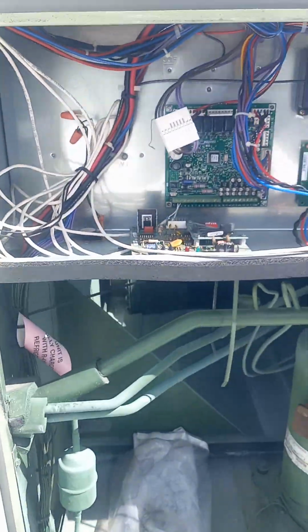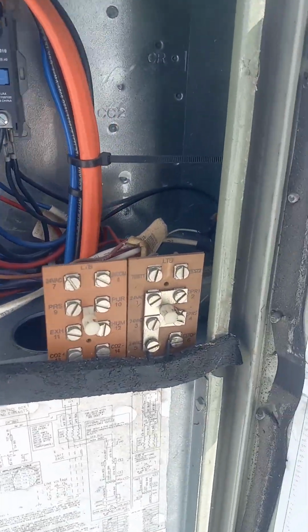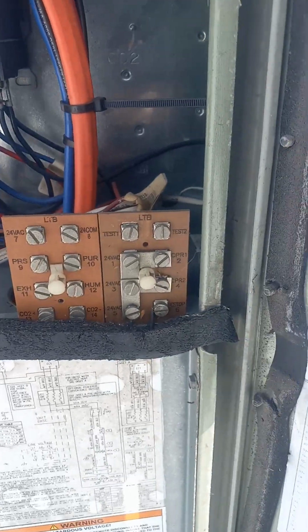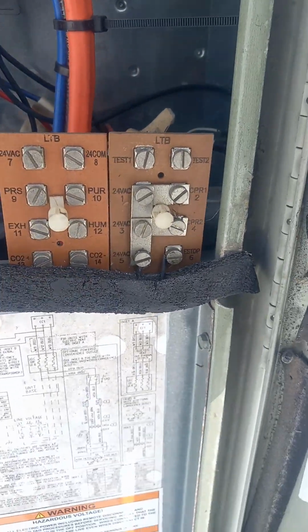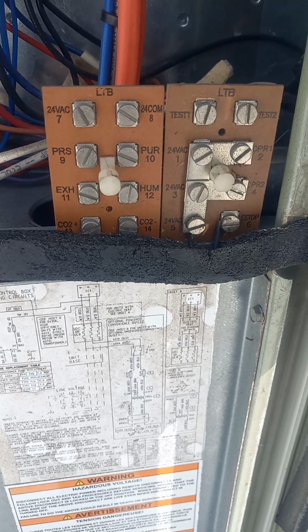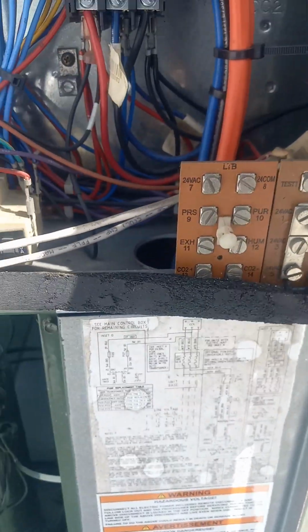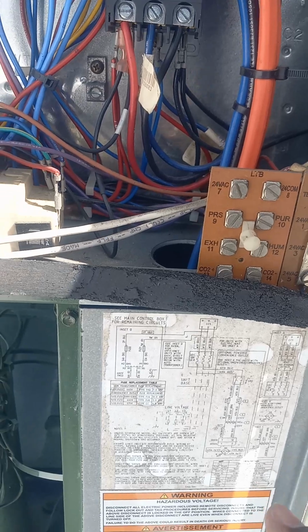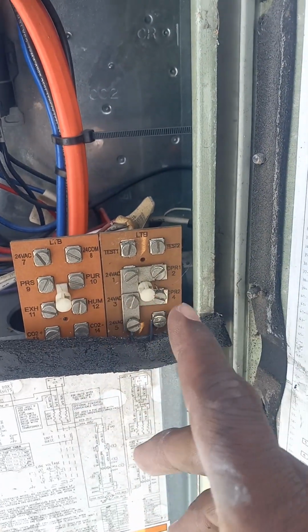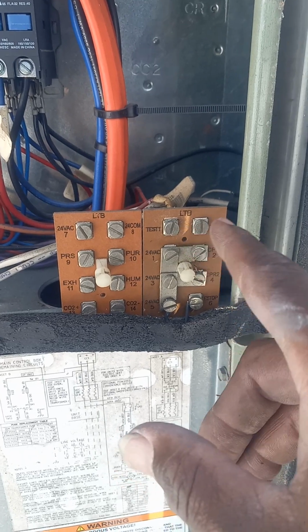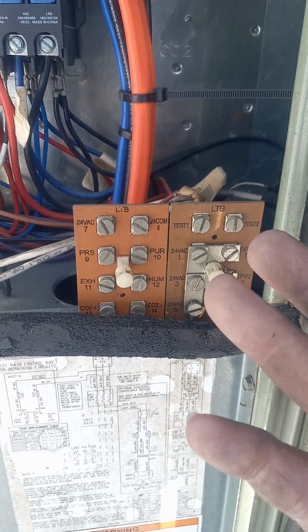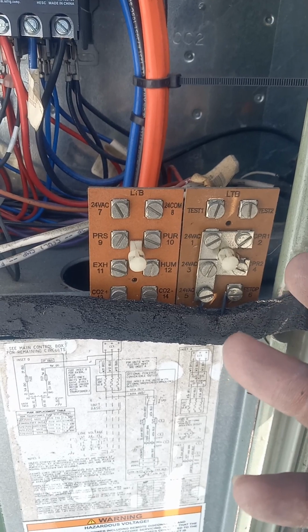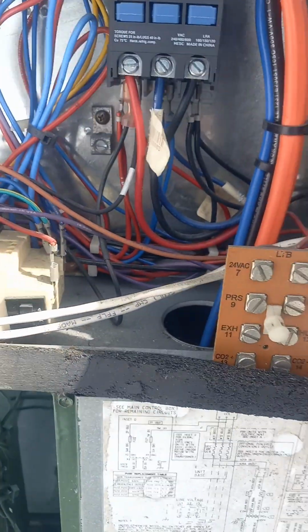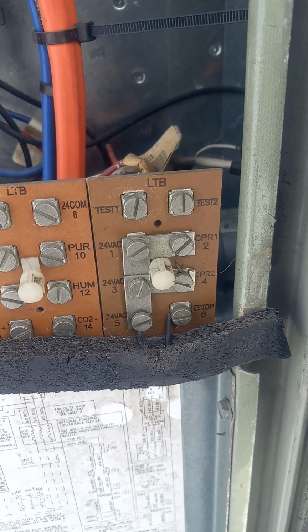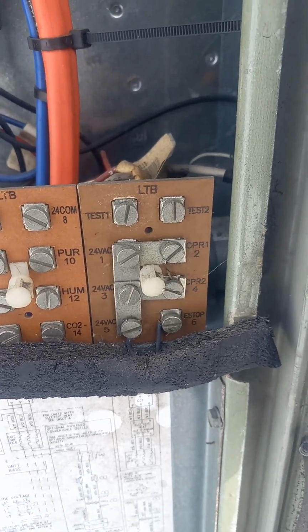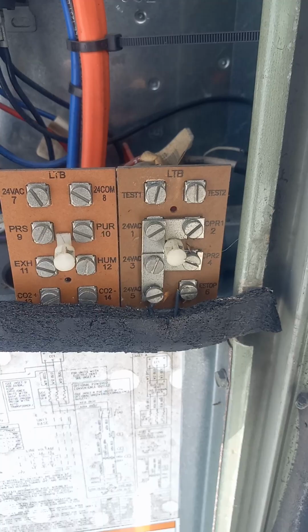All right. So you have the LTB boards, one the test board, and the other one you have the CO2 sensors, humidity, and all that stuff. All of these wires are connected together on the low voltage side, where you can put the unit into test from here by jumping out test 1, test 2, depending on how long you hold the jumper on that wire. Those wires are going to actually put the unit into test, whether it's going to be cool 1, cool 2, heat, dehumidification, and all that stuff.